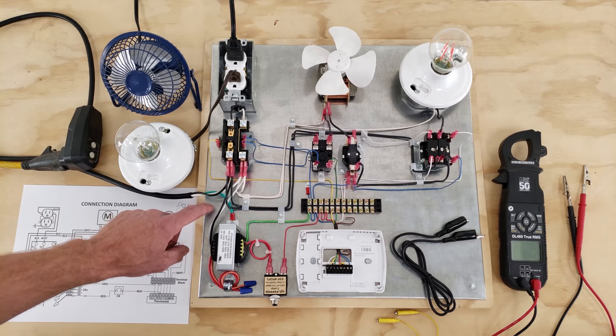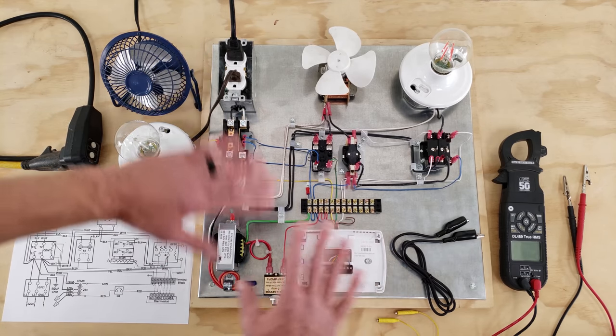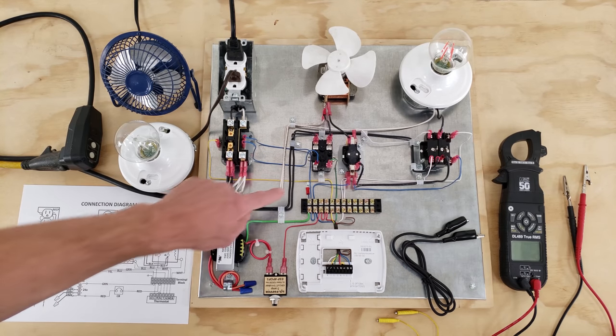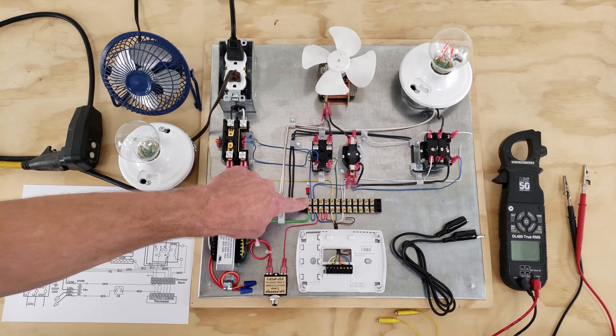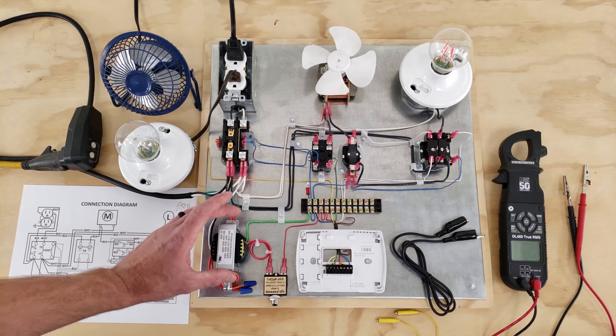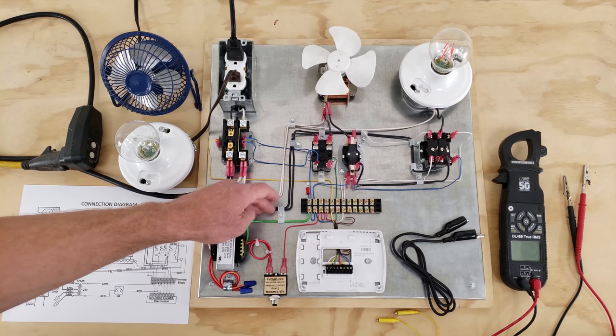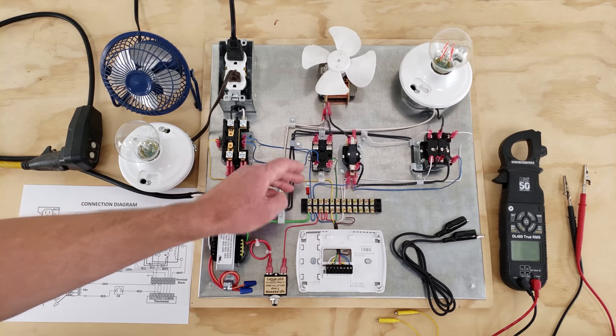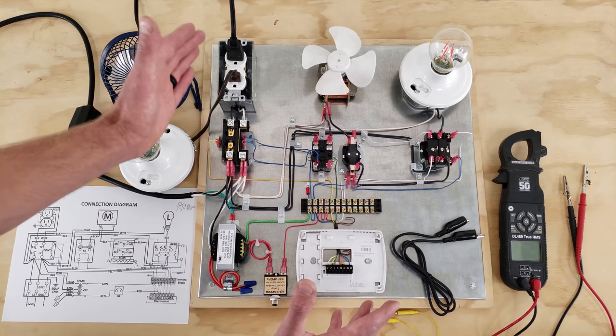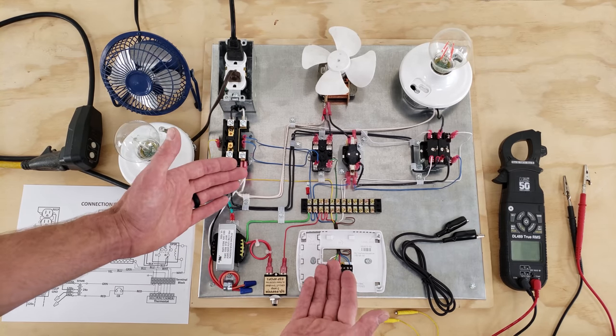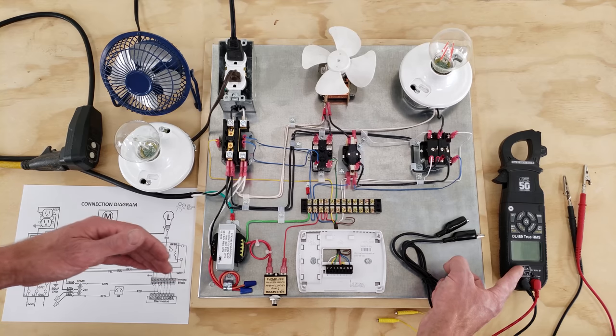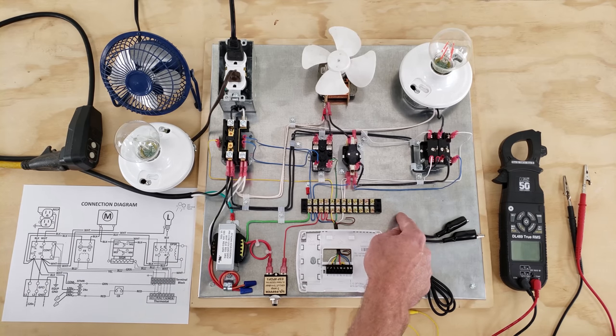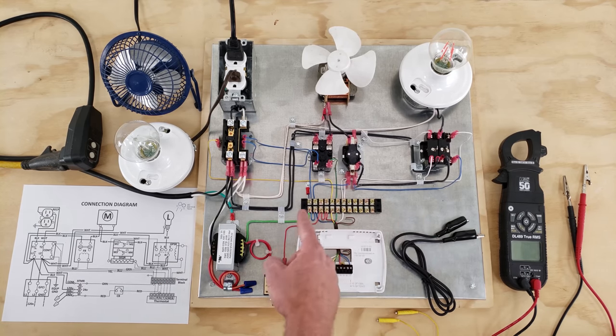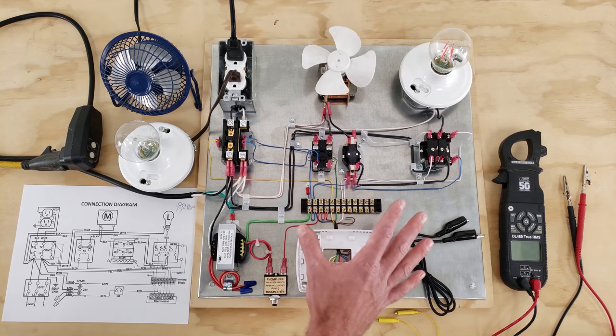On this board, let me just give you a quick little tour. This piece of sheet metal is the ground for this entire board. And we have our ground wire attached right here to our common. You've got to remember that your 24 volt transformer always has the common attached to the ground frame of the HVAC system. So that's almost all the time. And so you can utilize your multimeter, one probe on the ground frame and one probe on the hot wire, while you're tracing out your switches.